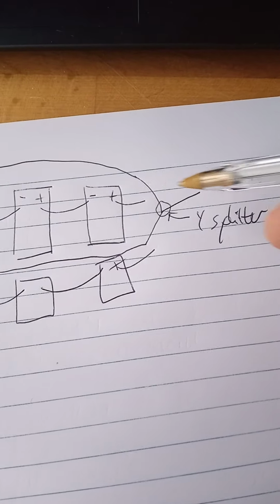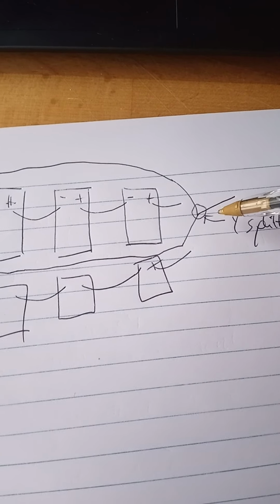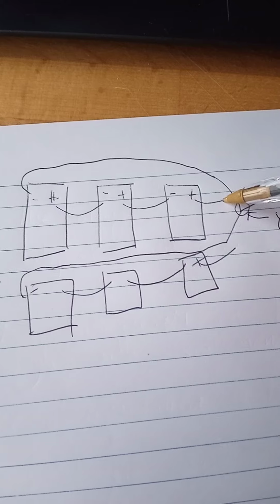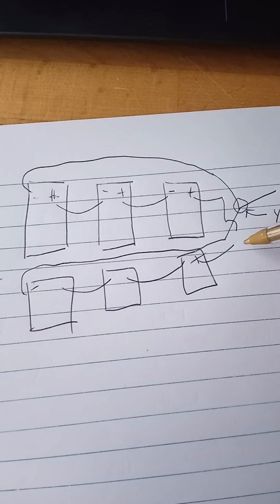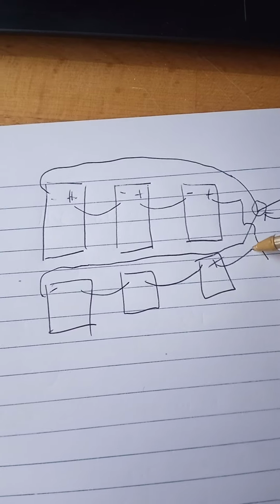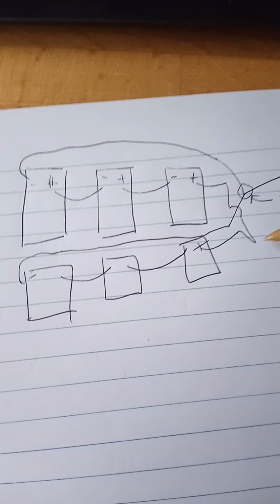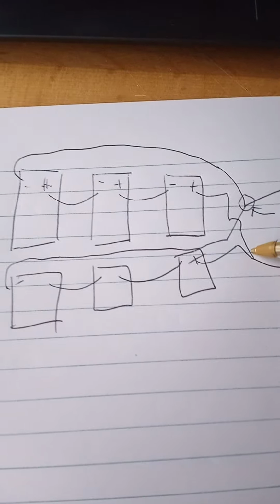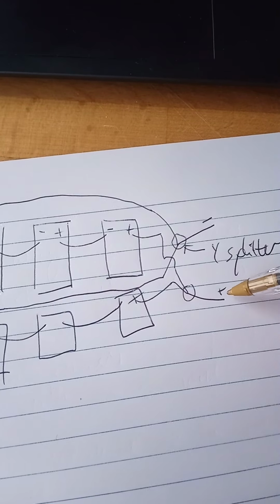Now you need to bear in mind, usually MC4s have a maximum amps rating of 30 amps. So when you're choosing how to do this, you need to think about the maximum rating of the weakest point in the system, which in this case is going to be your 30 amp MC4 connections. So up in voltage, down in amps, and that just means that the higher the voltage, the more panels that you can get on the string. So here's our other Y splitter. That gives us a negative and a positive going to the controller.